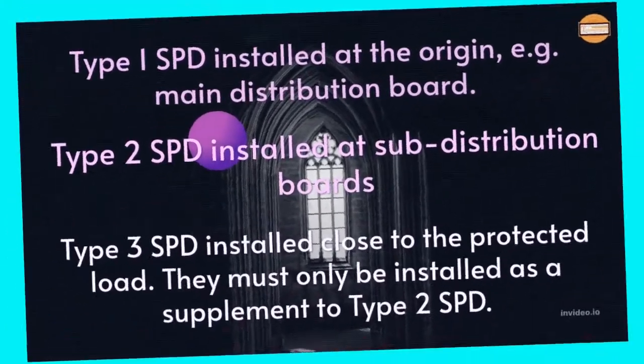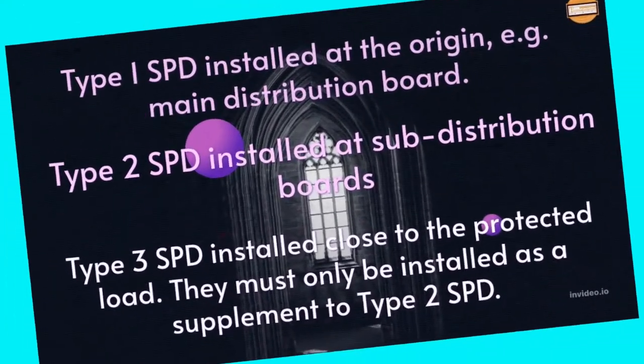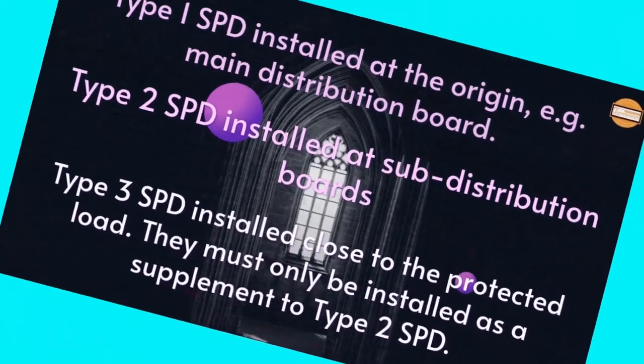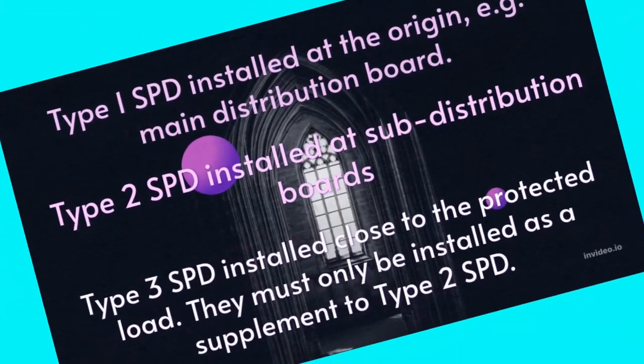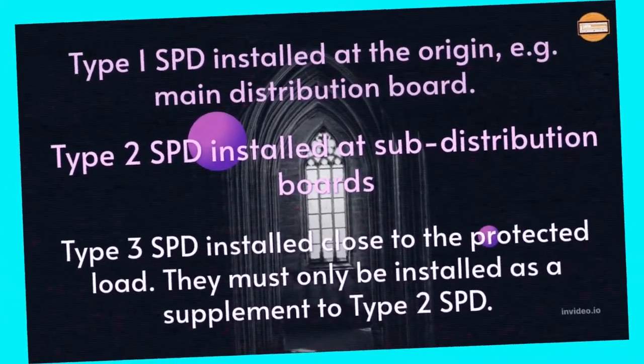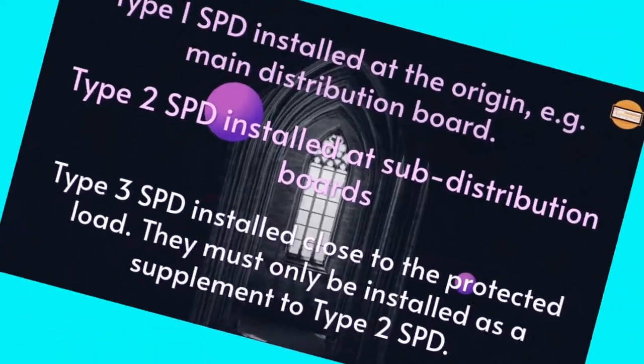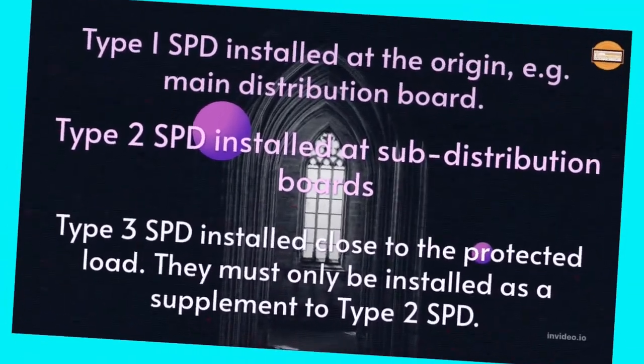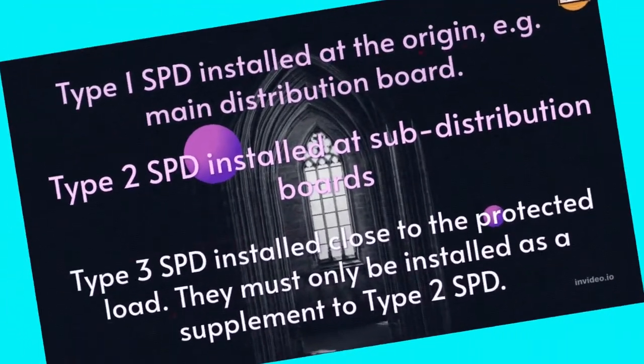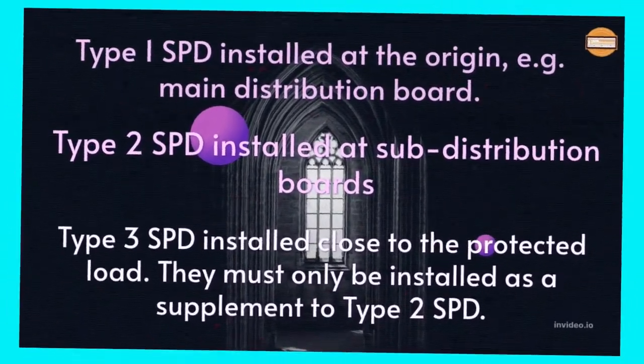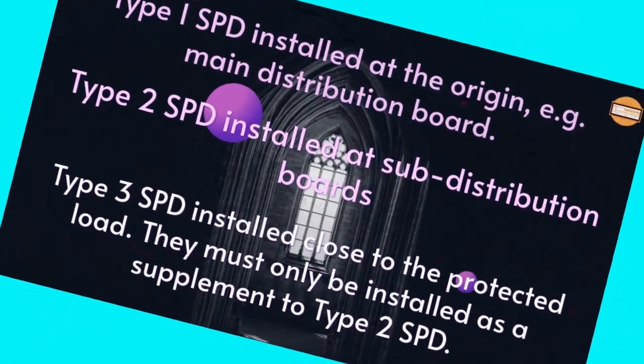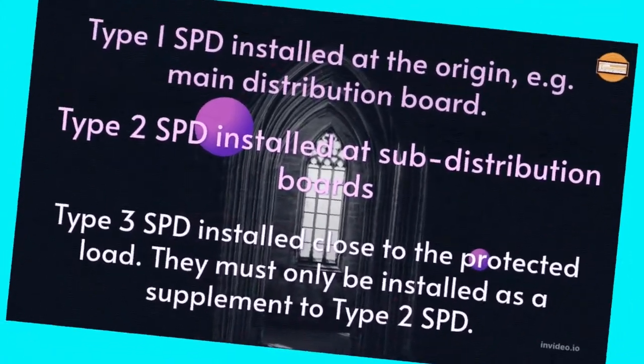Type 1 SPD is installed at the origin, that is, the main distribution board. Type 2 SPD is installed at sub distribution boards. Type 3 SPD is installed close to the protected load, and must only be installed as a supplement to a Type 2 SPD.